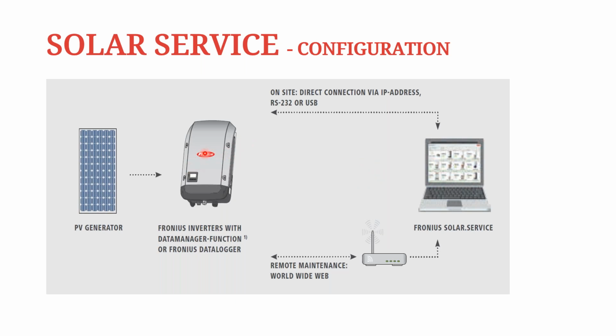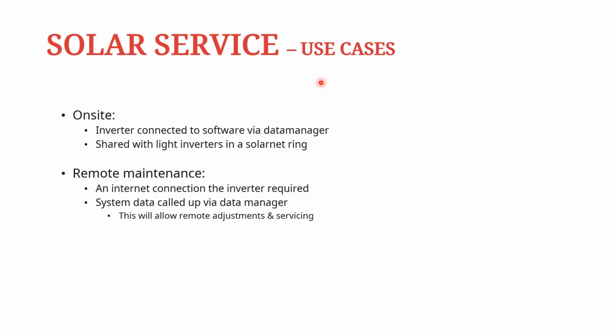And the requirement on the Fronius inverter is that it should have at least a Data Manager 2.0 in it, because this data manager card is the one that is going to facilitate the communication from the inverter to your laptop through the Solar.Service tool or software. And then if you are accessing it remotely, that connection will be completed through a router for an internet connection.